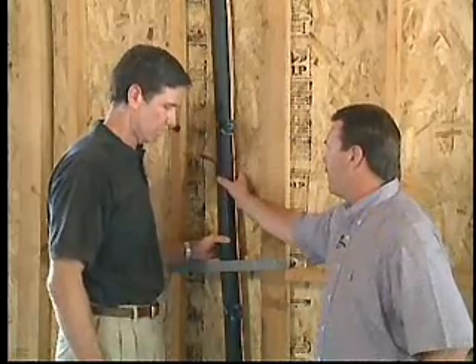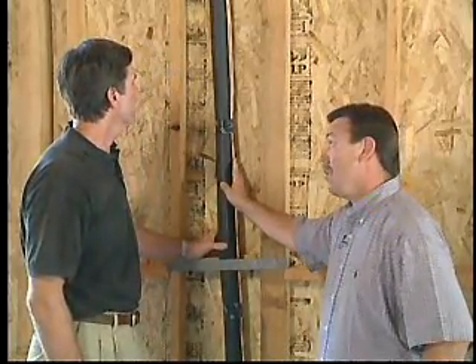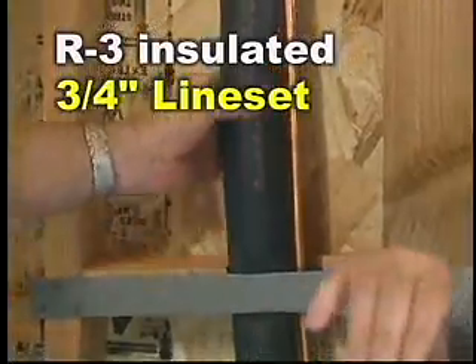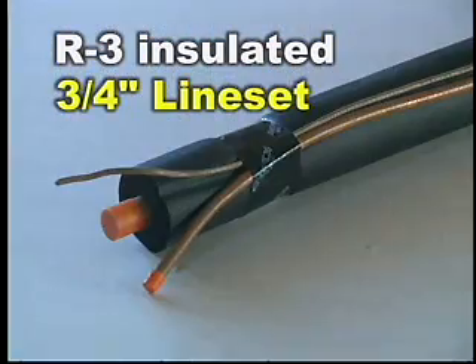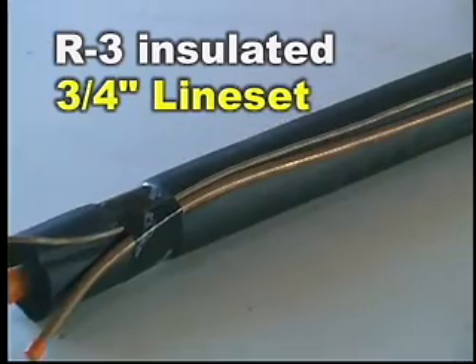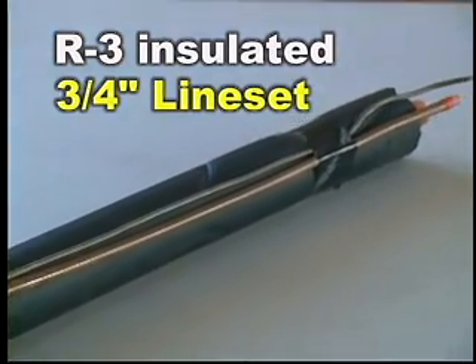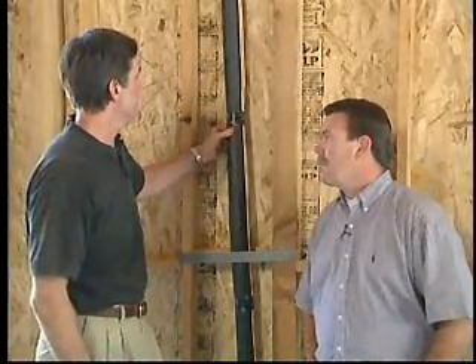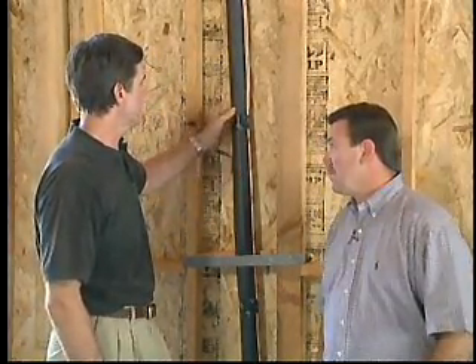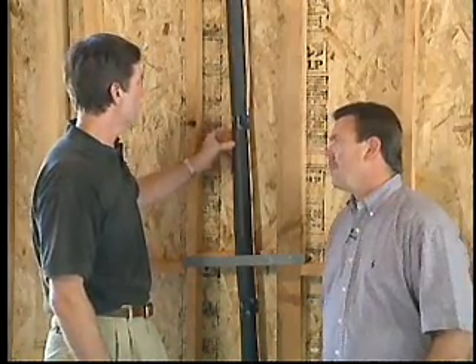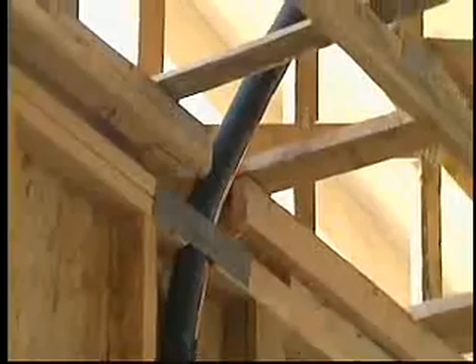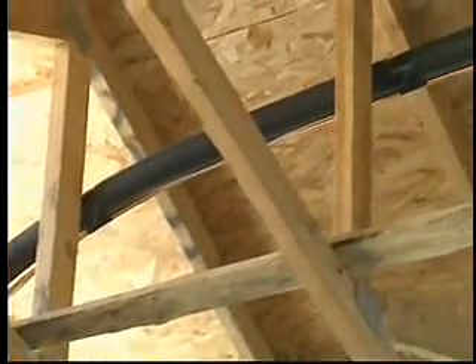Now, if you don't have R3 insulation, you have to make up for that in the wall, right? Right. Some of the manufacturers, if they miss the mark on hitting the R3 using the K factor and the R value, they do need to insulate. And this is kind of an ongoing review process at the CEC. We're trying to work with them to make sure that we could do something where perhaps this wouldn't be required. But for now, if you don't hit the R value, you'd actually have to come in here with some insulation and make sure it's in between the exterior wall, in this case, and the product itself. And that would hold true for the line set running through the attic. You'd have to do the same thing. Somehow encapsulate it in order to boost up that R value.